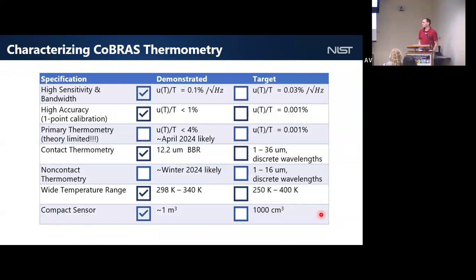With regards to the contact method for the thermometry, replacing the PRTs, so these fused silica or your vapor cell, compared to the material characteristics of these PRTs, what kind of thermal contact resistance issues might you run into, or has that been looked into?